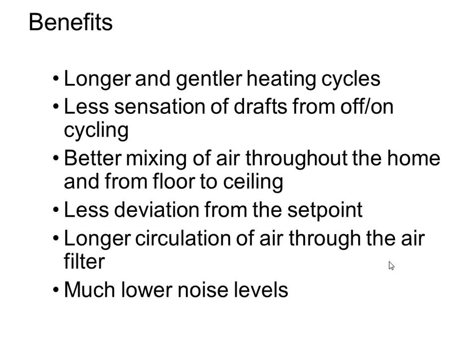And sound is actually improved as well. Because the gas valve is modulated down to a lower capacity at many operating points, the indoor fan is also modulated down to match that. So there's lots of hours we have where the fan is at a fairly low speed and very seldom ever has to ramp up to a quote-unquote high fire point.